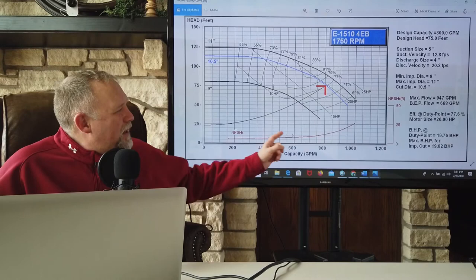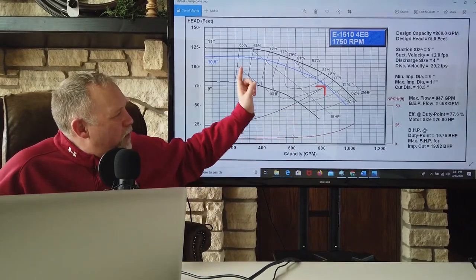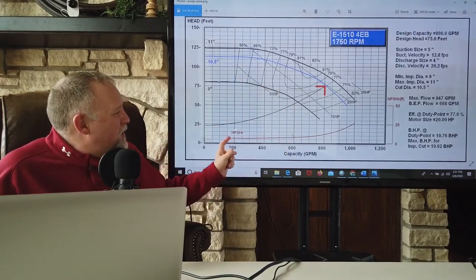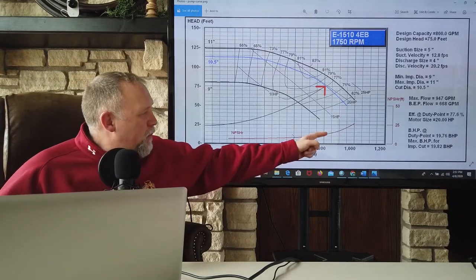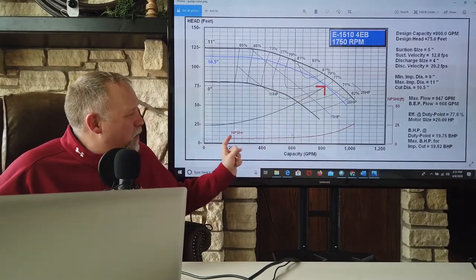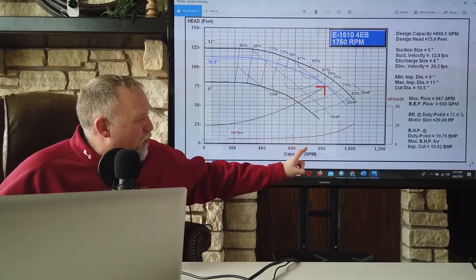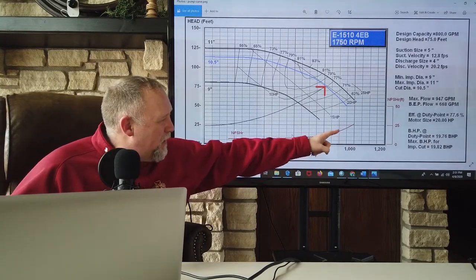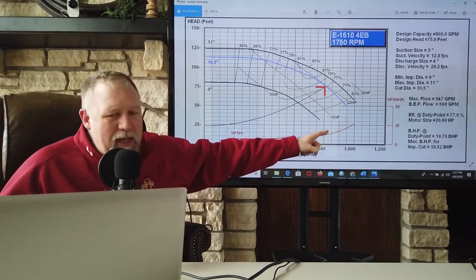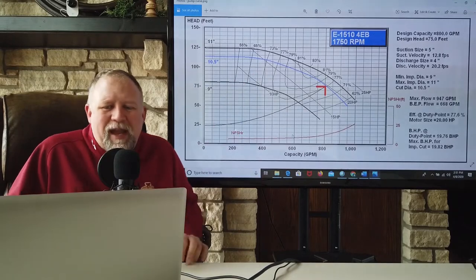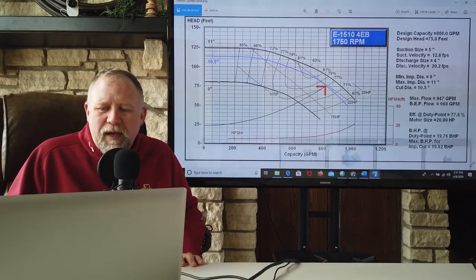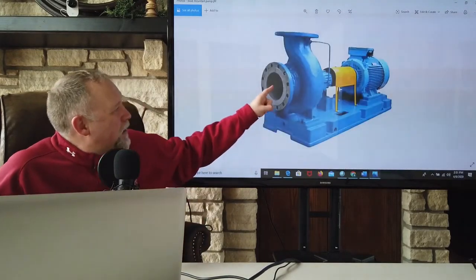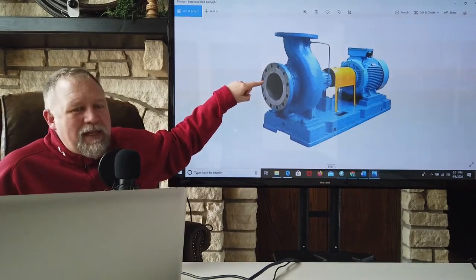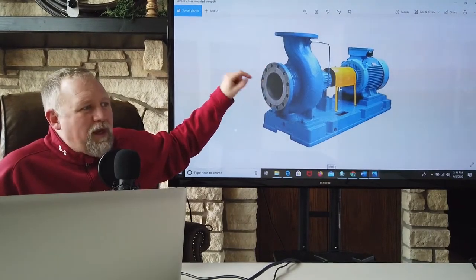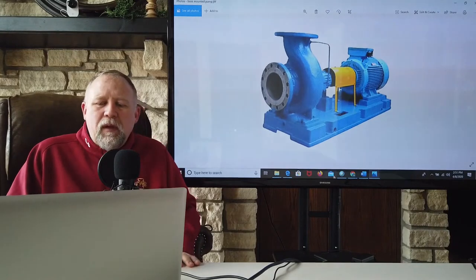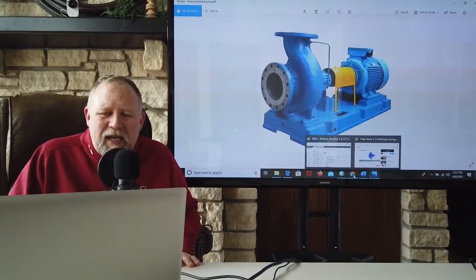That is the minimum inlet pressure that we have to have on that impeller to avoid something called cavitation. If we draw down, and this will usually happen when we have higher and higher flow rates, notice the minimum pressure on the impeller as we go further and further to the right at higher and higher gallons per minute, we have a minimum pressure on that inlet. Let's go back to our picture right here, that has to be maintained in order to avoid cavitation. All right, so what is cavitation?